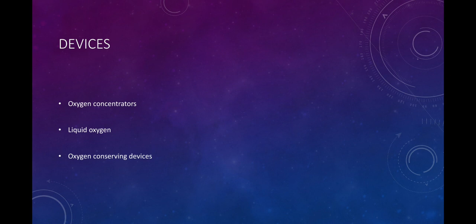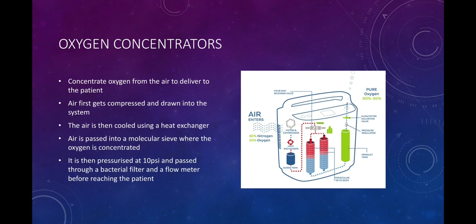Devices. There are 3 main devices: oxygen concentrators, which we use most commonly, followed by liquid oxygen and oxygen conserving devices. Oxygen concentrators concentrate oxygen from the air to deliver to the patient. The air first gets compressed and drawn into the system, where it is cooled in a heat exchanger. Air is then passed into a molecular sieve where the oxygen is concentrated. It is then pressurized to 10 psi and passed through a bacterial filter and a flow meter before reaching the patient.